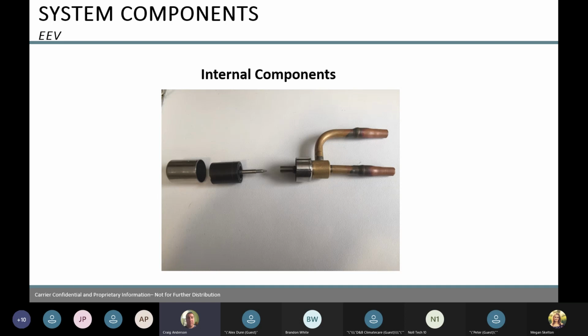Failure comes from what's going through it, your Freon, because inside your EE valve there are little screens, and if they get blocked, or if something has been added to the system, like dye, or somebody put Loctite on the nuts outside and it got in the system, this is where we're seeing failure of EE valves, TX valves or reversing valves: stuff has gotten into the system.